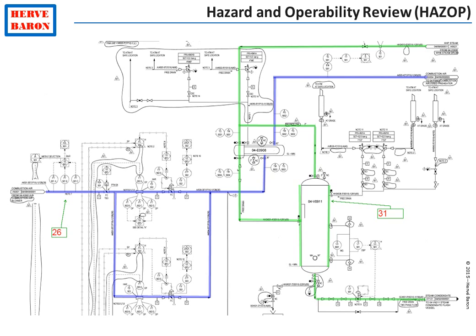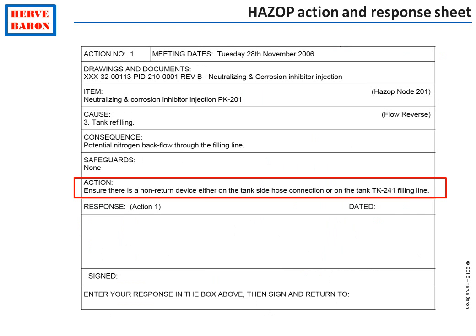Such a safeguard could be a hard device like a pressure safety relief valve, or a soft device such as an instrumented safety function. If there is none, then the HAZOP will request an action from the engineer by issuing a HAZOP Action Sheet, which shall be answered and closed out by the engineer.